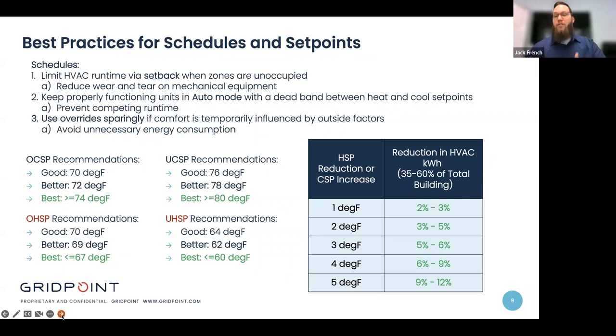And these settings, especially best practice, are going to reduce the runtime of your HVAC equipment, which in turn, like I keep mentioning, reduces unnecessary wear and tear and extends the life of your equipment. Then when the spaces are not occupied, the units can go into an unoccupied cooling mode. So we can increase the cooling set point since no one is in the space.